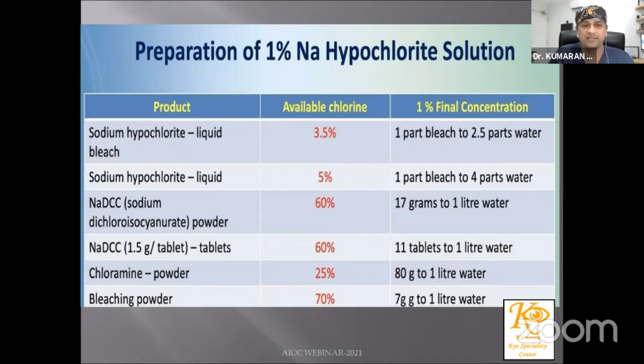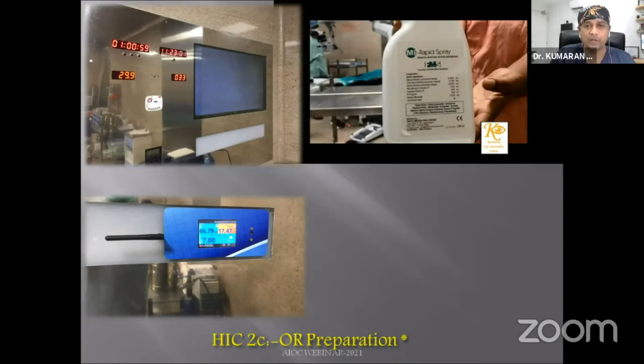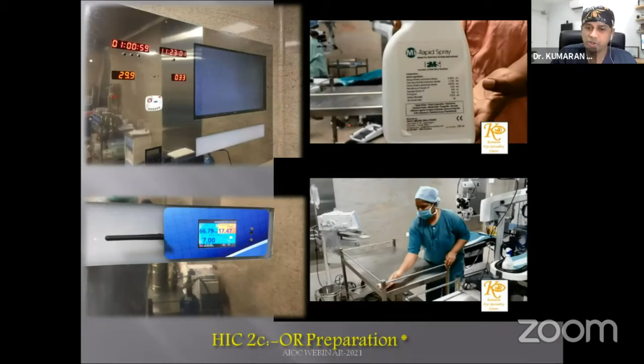So before you enter into your theater, make sure that you switch on the air conditioning to reach the parameters of temperature and humidity at least 1 hour before you enter your theater. Make sure all the parameters are complete before you enter your theater. And once you enter, make sure you use an aldehyde-free, alcohol-based disinfectant and a clean, lint-free cloth to wipe all the surfaces, making sure that you don't use the same side of the lint-free cloth to wipe repeatedly.